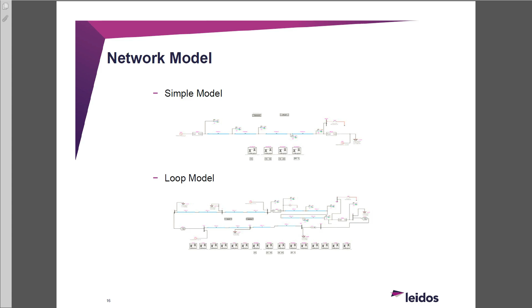Okay, we're going to take a line out. So what do I measure? It's good to measure local, remote, and to split the line. We usually split it 3 times depending on the length. If the line is too long, you can split it to get halfway, two-thirds of the line, to check the TOVs across the entire line. That's something we usually recommend, different lengths, to cut the line in between.